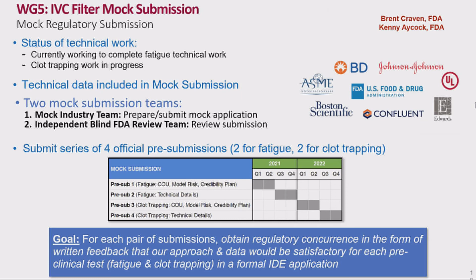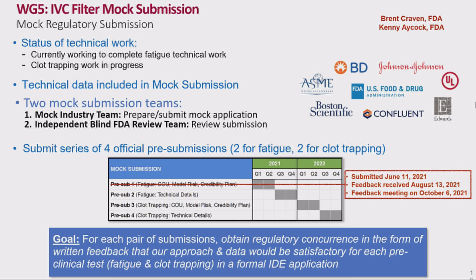So the M&S is targeting 2 of the most burdensome preclinical bench tests. It's really trying to replace bench tests in that case for fatigue resistance and for clot trapping. I won't get into detail of that. And the status of the technical work: I mentioned a number of companies are involved. There are 2 mock submission teams. Mock submission team 1 prepares and submits the mock application, and the independent blind FDA review team reviews that. For each of the 2 pairs of submissions I mentioned, we get feedback from the FDA. So pre-sub 1 is completed. We're going to pre-sub 2, and we haven't started with the FDA yet. So it's fatigue and CFT. You can see structural and fatigue have covered probably the 2 more frequent in the domain of modeling and simulation technologies.